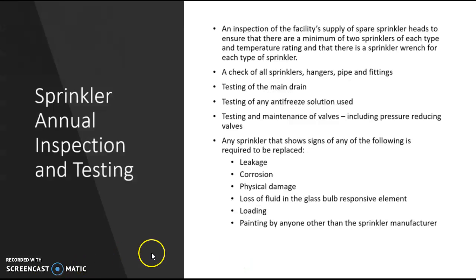An inspection of the facility supply of the spare sprinkler heads to ensure that there are a minimum of 2 sprinklers of each type and temperature rating, and make sure that there's a wrench in there that you can change it out with. All sprinklers, hangers, pipes, fittings, all the system needs to be checked over and make sure that nothing is hanging, nothing is broken, everything looks good.